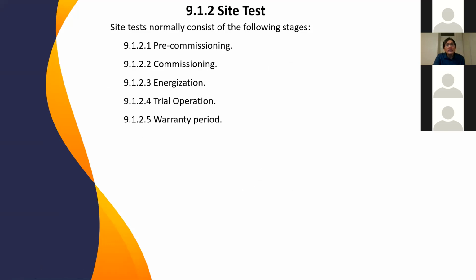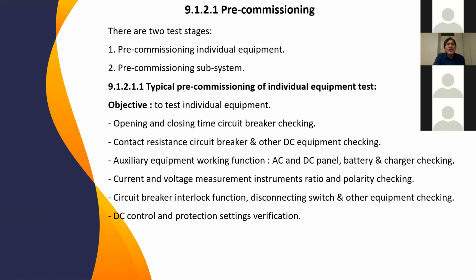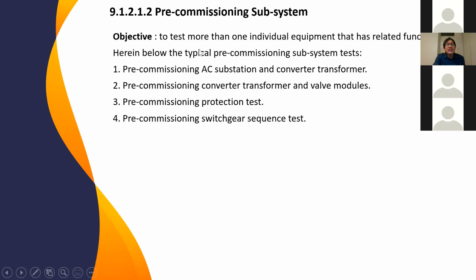Now we move to site test. There are 5 types of site tests: pre-commissioning, commissioning, energization, trial operation, warranty period. For pre-commissioning, we have two types of tests to be done: individual equipment and pre-commissioning subsystem tests. The pre-commissioning individual tests test equipment by equipment, while subsystem tests test more than one individual equipment, or functions related to each other. For instance, here, commissioning AC substation with converter station, or converter transformer with valve, pre-commissioning protection test, pre-commissioning switchgear sequence test.